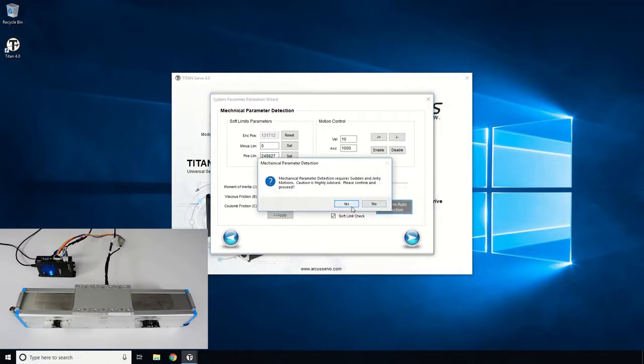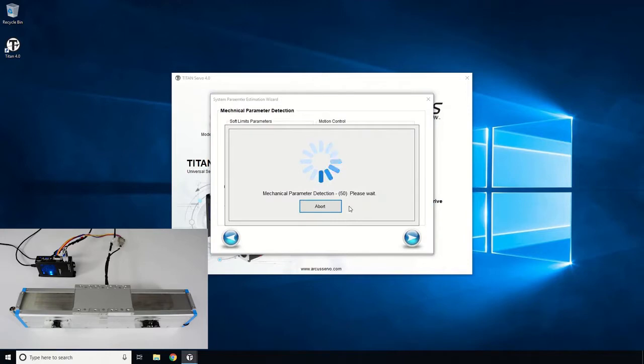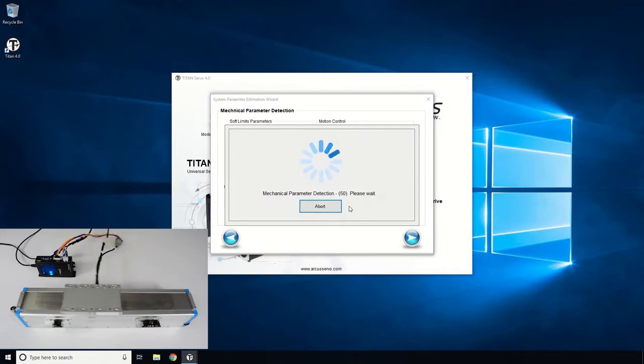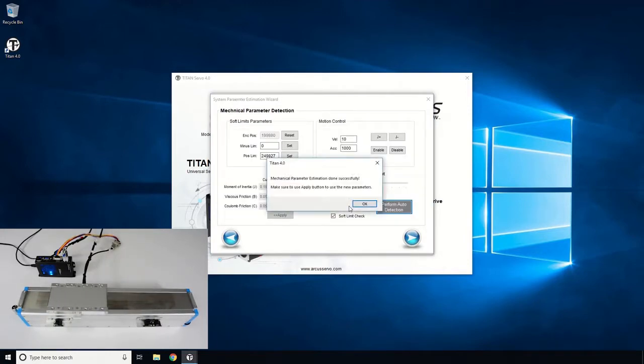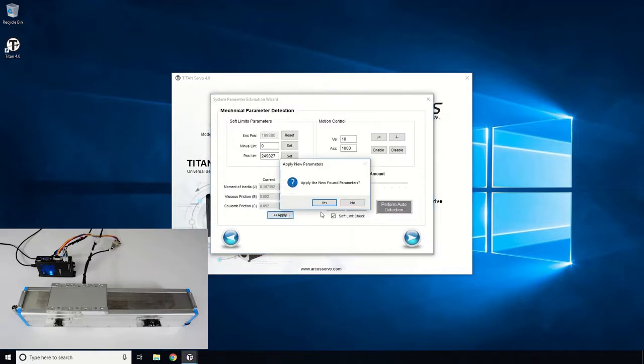The motor will energize and perform short, high acceleration moves in order to calculate the inertia and the two friction parameters. Once the detection sequence is completed, click the Apply button to use the newly found values for the next sequence.